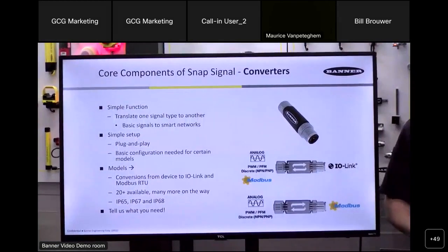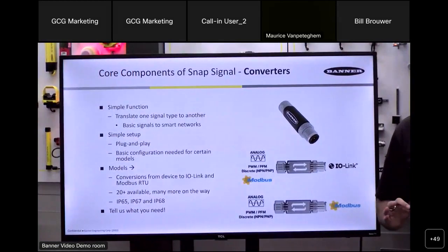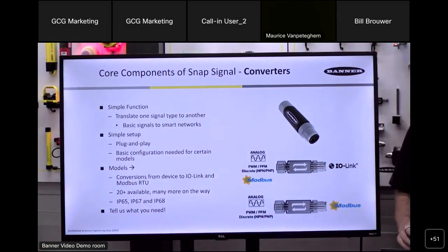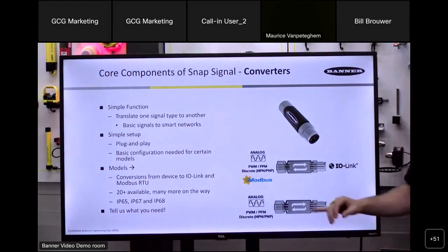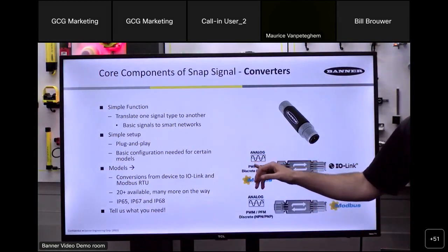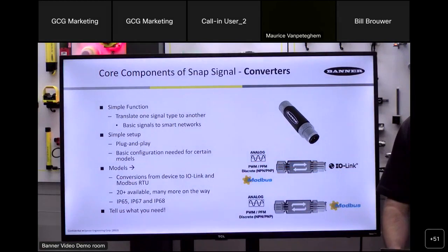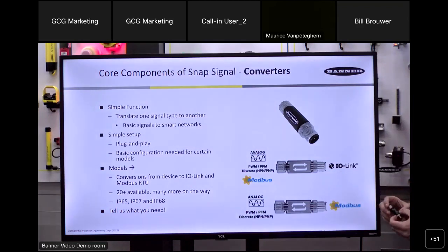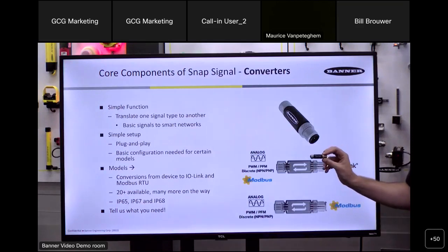We have two different styles: converters that convert over to Modbus RTU, the RS-485 protocol, and converters that convert over to IO-Link. This lets us take legacy sensor signals that are all over the world of industrial automation, signals such as analog 4 to 20 or 0 to 10 volt signals, and NPN or PNP signals that might be coming from a proximity sensor or a photo eye, and convert those signals over to either Modbus RTU or IO-Link.